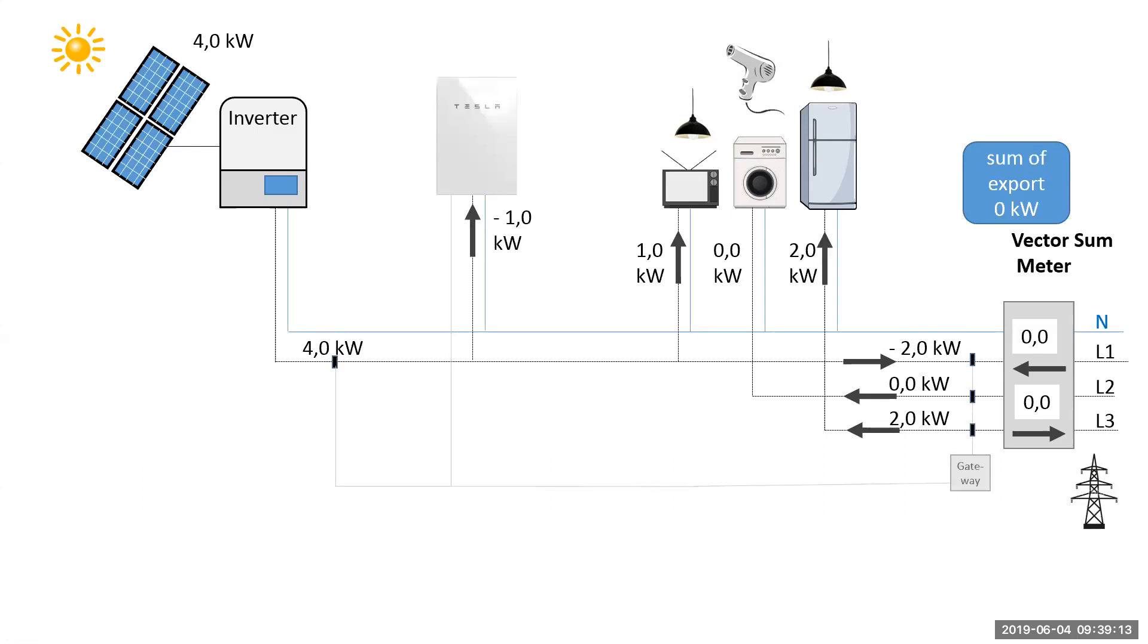That battery will see that there is one kilowatt going out to the grid and it will pull it in into the battery, therefore keeping the vector sum meter at zero. It would still be exporting two kilowatts out on L1 and you'd be pulling the same two kilowatts in on L3, leaving the vector sum meter to be zero.